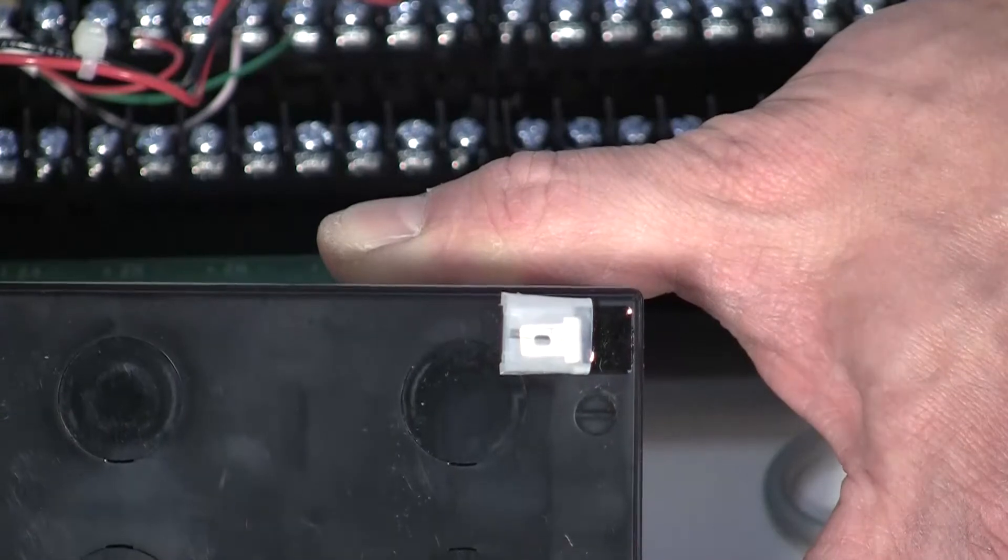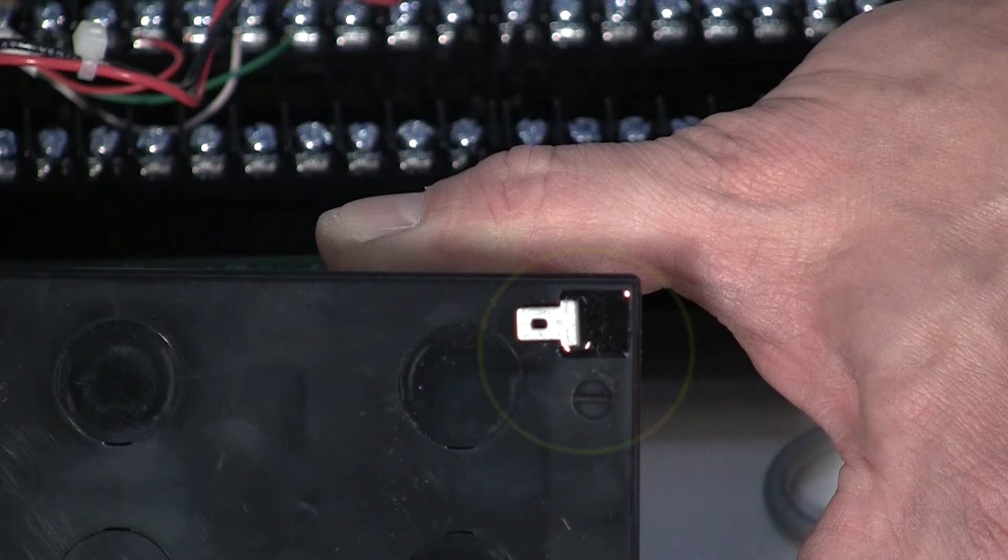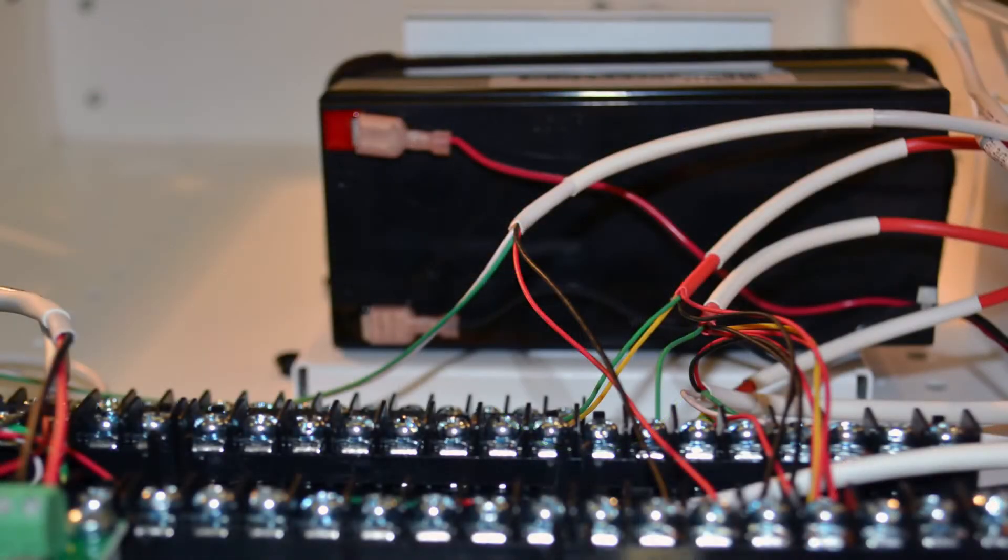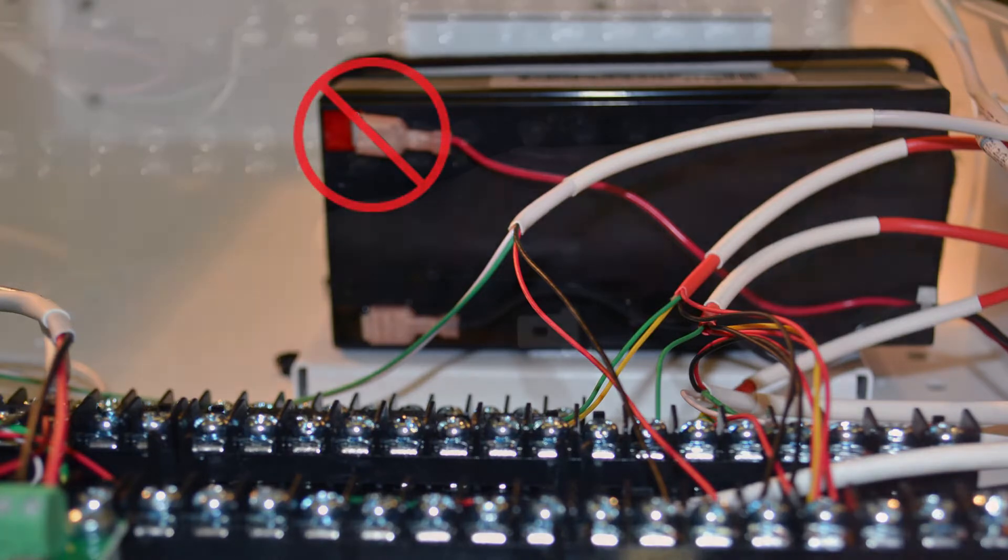Next, we are going to address the battery. Initially, we want to connect the black battery wire to the minus terminal on the 12V 7Ah battery. Do not connect the red wire at this time. Do not reverse these connections or the battery fuse will blow.